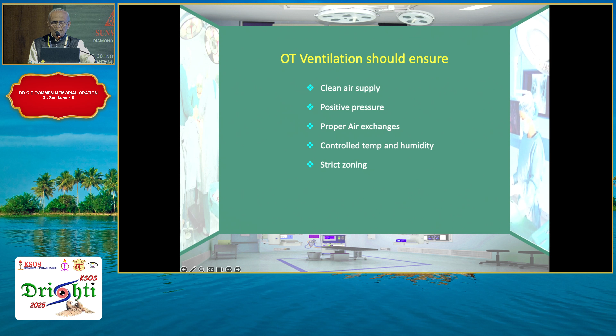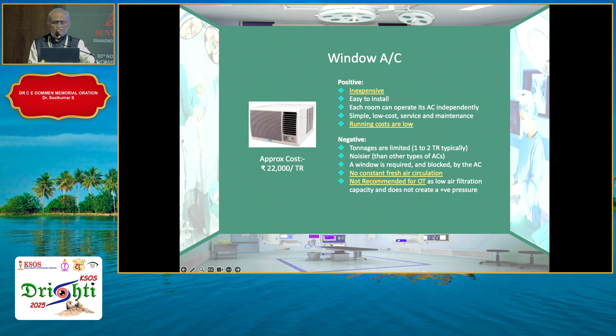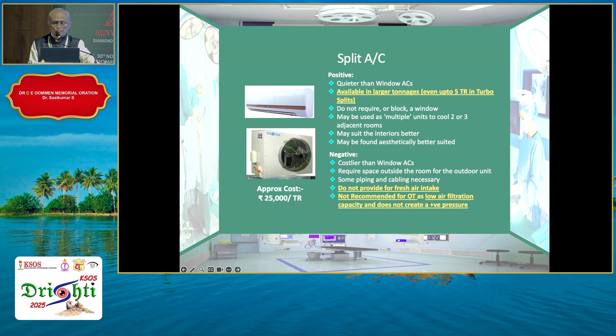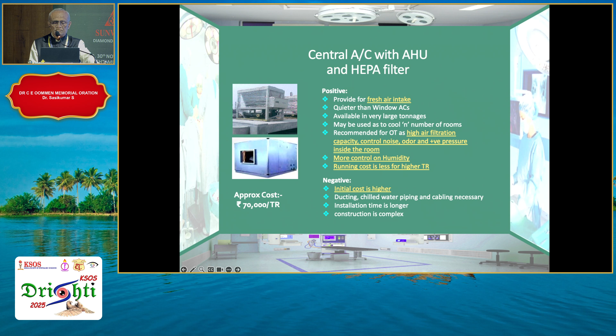Proper layout and ventilation ensure that there is a differential, decreasing positive pressure ventilation gradient from the inner to the outer zones, so that the cleanliness gradually increases from the protective zone, or the outer zone, to the operating room. Window AC is recommended only for comfort settings and not for critical zones. Split AC has no fresh air intake, as I have mentioned before. Other than cool air, the other objectives of ventilation are also not met with split AC. Independent ductable units or direct expansion units are ideal for all small setups. Central AC has a very high establishment cost, but the long-term running cost is less.